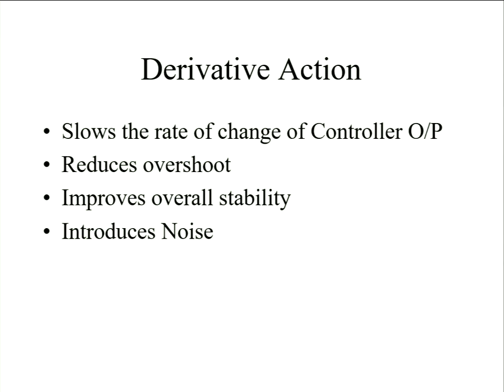and so you can tune up perhaps using PI control anyway. And again, if I was using a compressor, I wouldn't necessarily want to be asking it to make lots of small changes in speed up and down. So I must admit I've never actually come across anybody using P plus D on its own, but in principle you could do. How easy is it to set those parameters, the K parameters? Well, that's where we'll talk about the tuning rules, but it can be difficult.